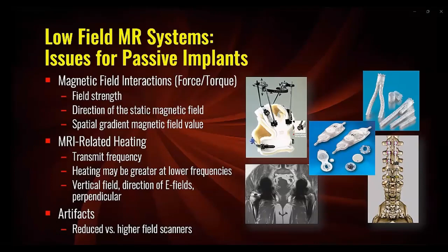I previously mentioned that consideration should be given to the spatial gradient magnetic field information with respect to implants and devices, so I'd like to make a few important points about this variable. It should be noted that the spatial gradient magnetic field is the field that varies in intensity over distance. When an implant is assessed for force, the test apparatus with the implant is placed at the point of the highest patient-accessible spatial gradient magnetic field. When such testing is performed, the implant is suspended by a string and therefore it is freely able to move in space. The resulting information is the value of the spatial gradient magnetic field that was used for the force test, and that information becomes part of the MRI labeling for the implant.